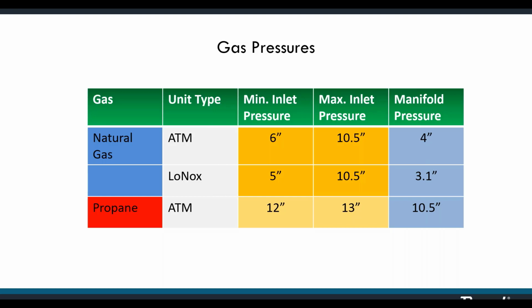Here's the thing, man. I know a lot of guys, they just, hey, I'm replacing a 400,000 BTU heater with another 400,000 BTU heater. I'm sure it'll be fine. Will it? Is it going to be fine? Is it just possible that maybe a problem with proper gas flow is what caused the old heater to fail in the first place? Check it when you install it. At least you'll know it was right that day. Okay. And again, those are your pressures. Now, again, we're looking at the low NOx model today. So 5 to 10.5 coming in, and you're going to get 3.1 on the other side.